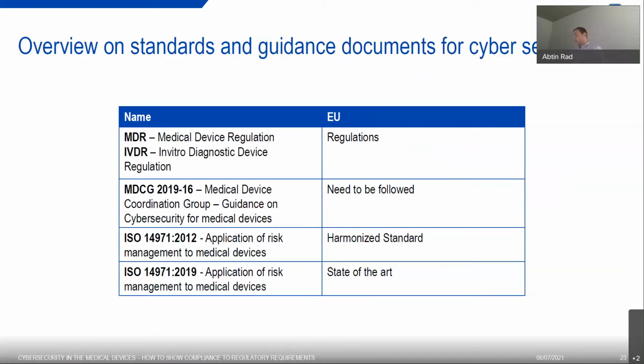The security risk management process, which was recently updated in 2019, is a core part of the development lifecycle of a medical device, and there you need to consider risks that are associated with the medical device. The update in 2019 also includes risk associated with data security, data privacy, and cybersecurity. And the authors of the standard go as far as to explain that there is no separate process necessary for the management of security risk in medical devices. So basically, you can stick with this risk management process, 14971, and you should also be able to consider cybersecurity risk.